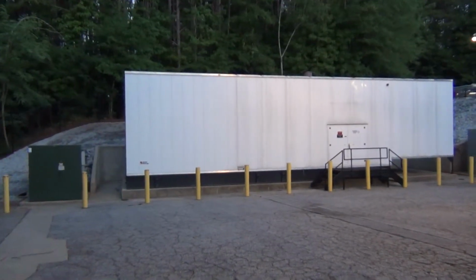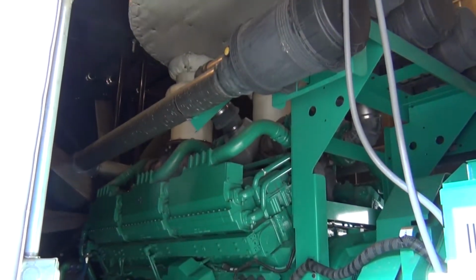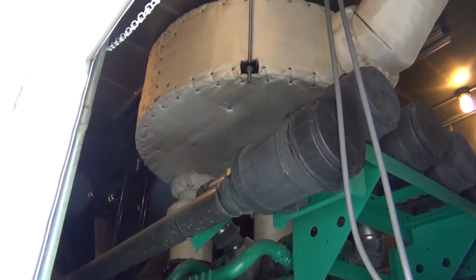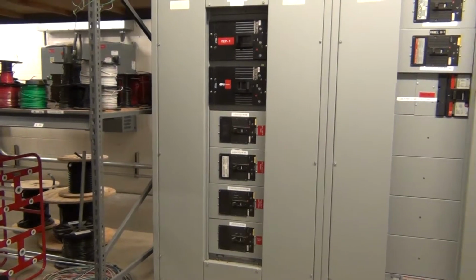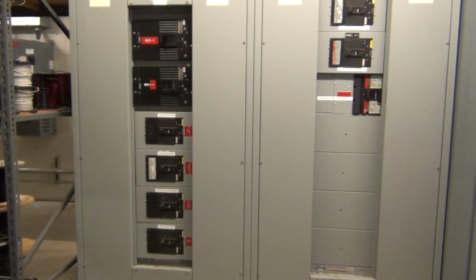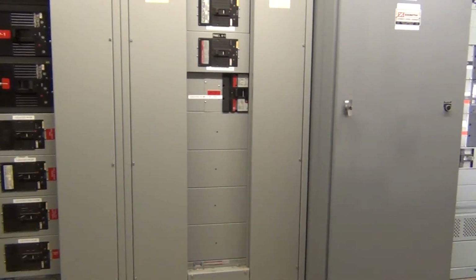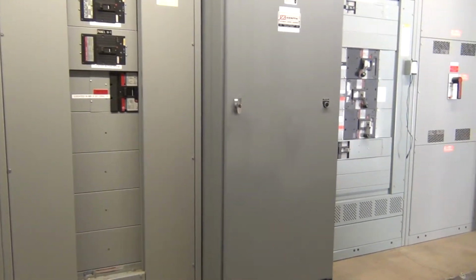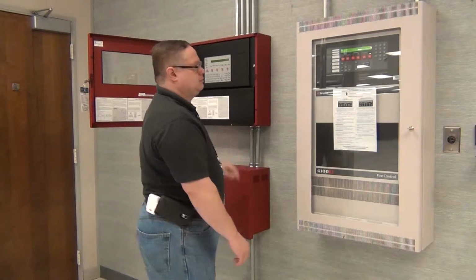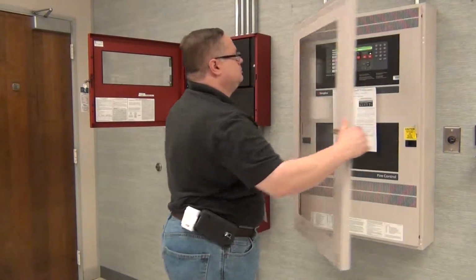We have currently 4.5 megawatts of aggregate power, a 2 megawatt A side, a 2.5 megawatt B side, backed by generators slated to run 24 hours on the fuel on hand. Power is conditioned by 4 UPSs: three 675 kilowatt and one 180 kilowatt.